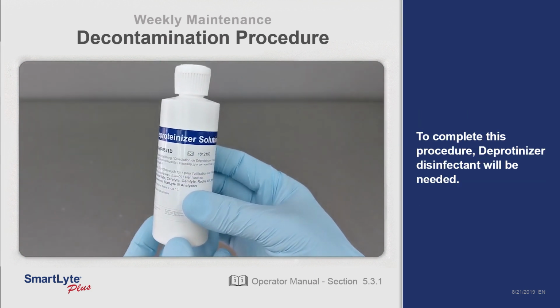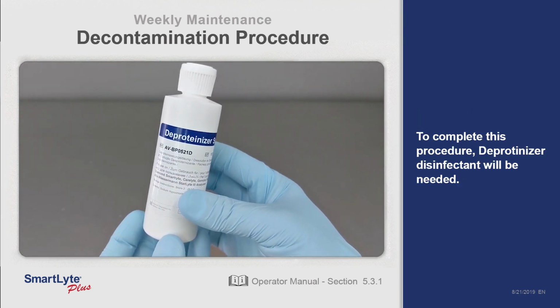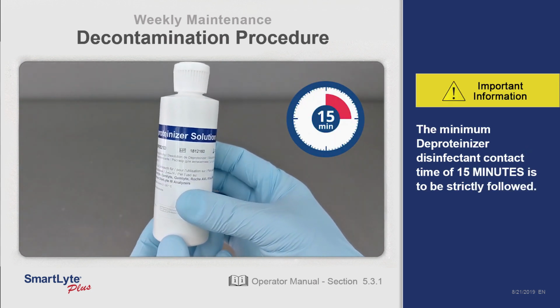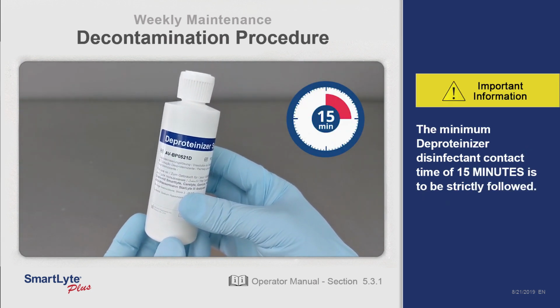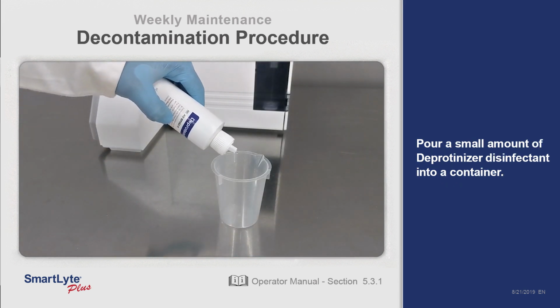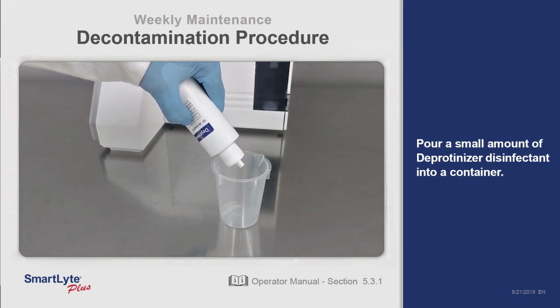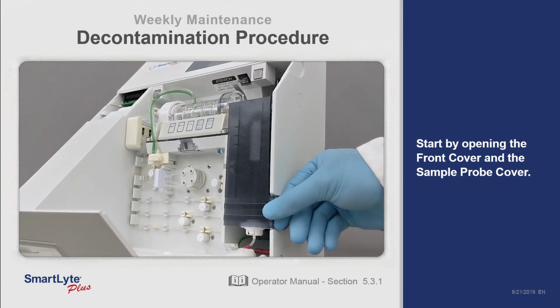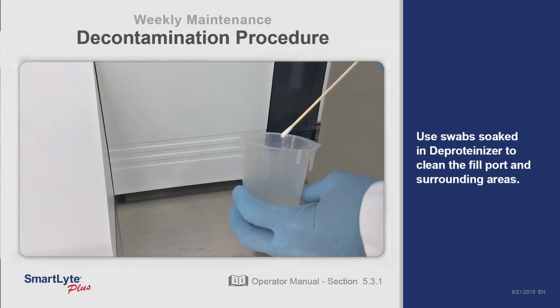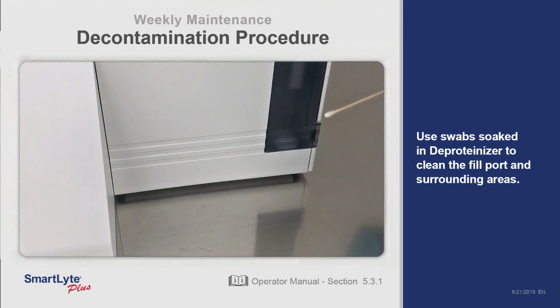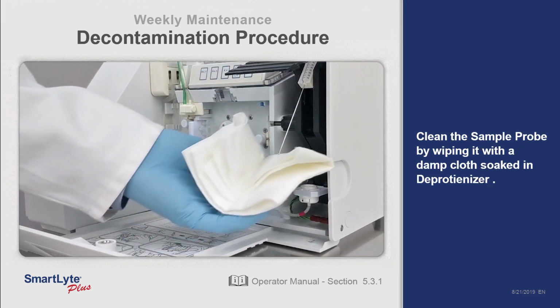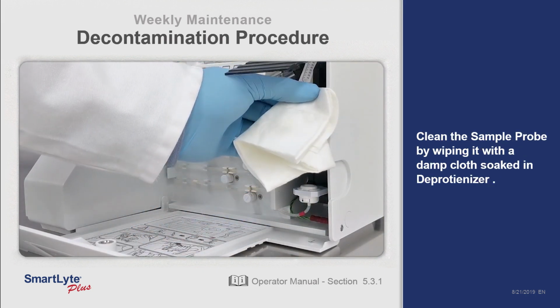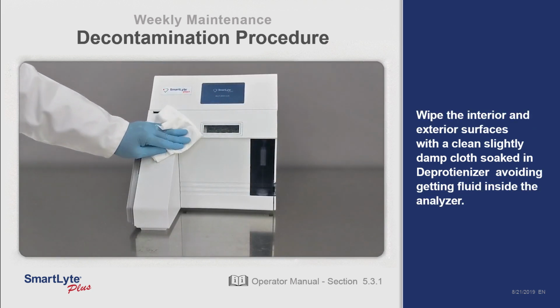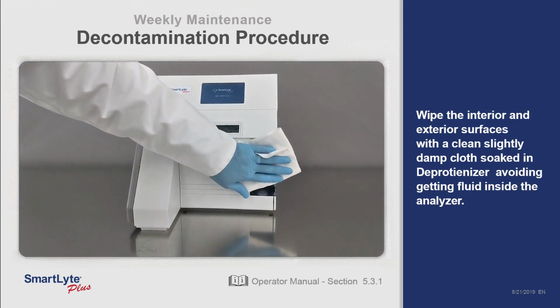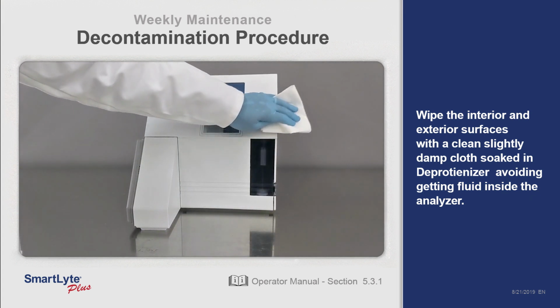To complete this procedure, Deproteinizer disinfectant will be needed. The minimum Deproteinizer disinfectant contact time is 15 minutes and it's to be strictly followed. Pour a small amount of Deproteinizer disinfectant into a container. Start by opening the front cover and the sample probe cover. Use swabs soaked in Deproteinizer to clean the fill port and surrounding areas. Clean the sample probe by wiping it with a damp cloth soaked in Deproteinizer. Wipe the interior and exterior surfaces with a clean, slightly damp cloth soaked in Deproteinizer, avoiding getting fluid inside the analyzer.